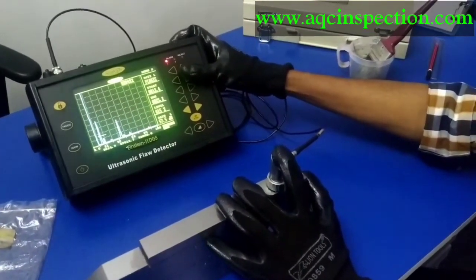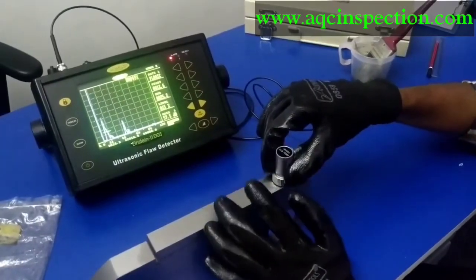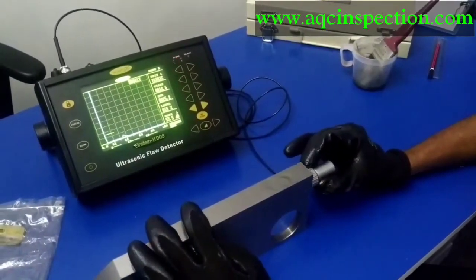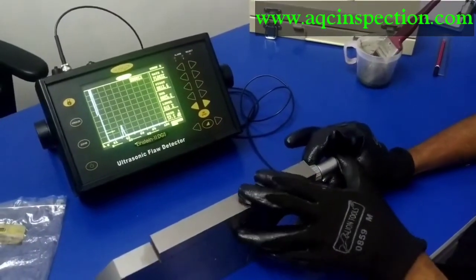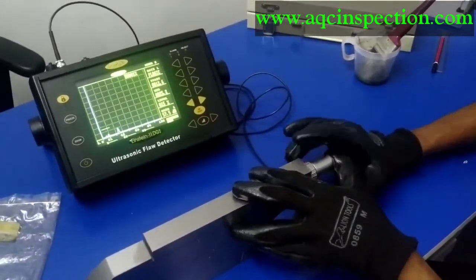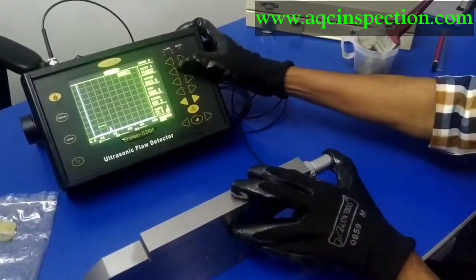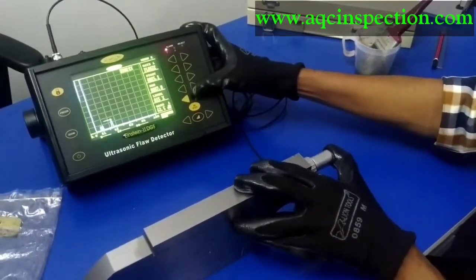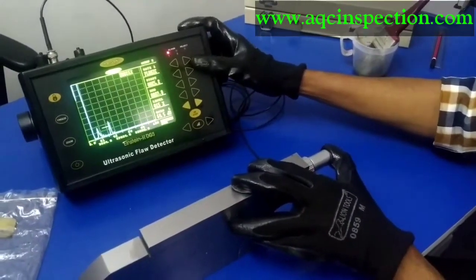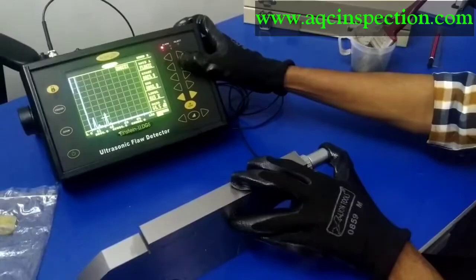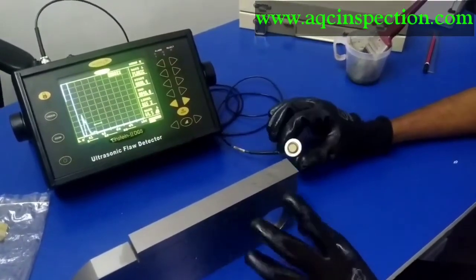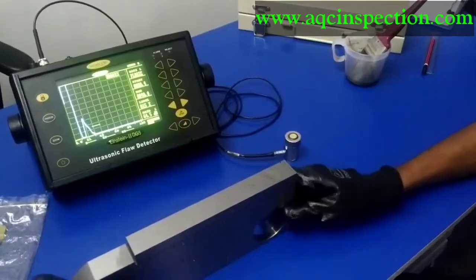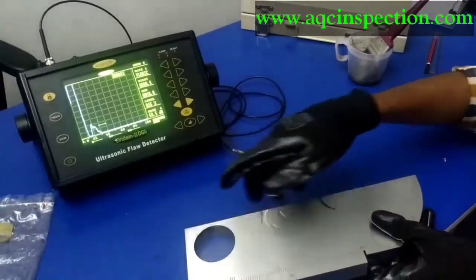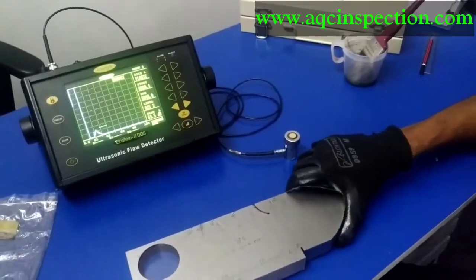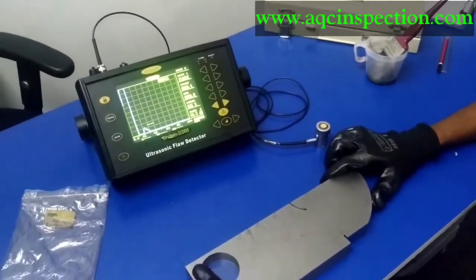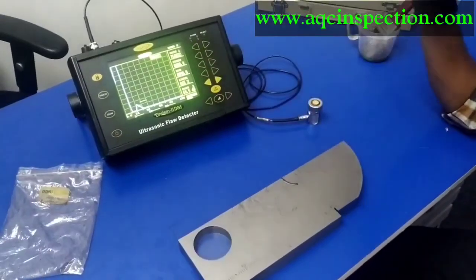It is 14.7 mm, which is the first side drill hole signal, and I'll place the gate right here to get the 35 mm signal. Yes, I'm getting it. And move the gate, also increase the gain value. I'm getting 34.8 mm. This is how you check for the sensitivity calibration. And the last step that I'm going to be doing right now is, it's not the last step, there's one more step. What I'm going to do right now is calibrate this plexiglass to the required velocity.